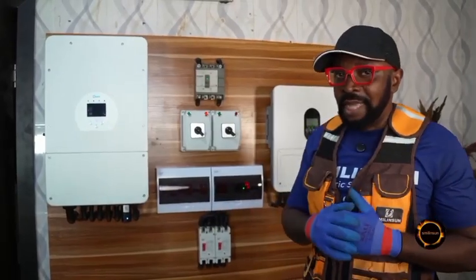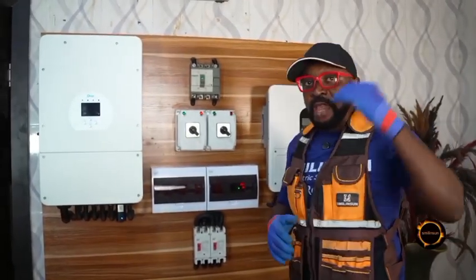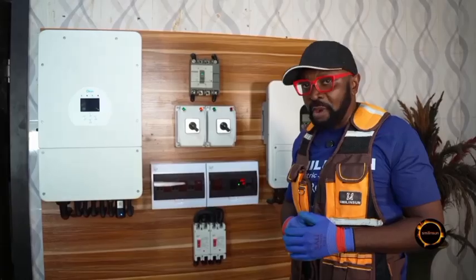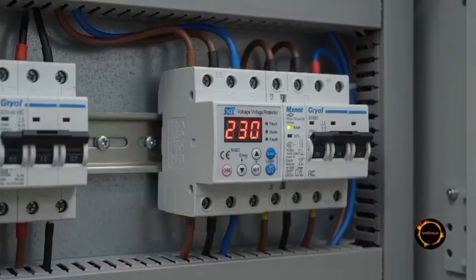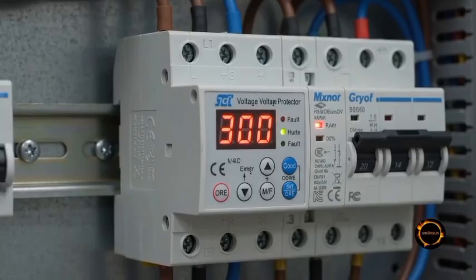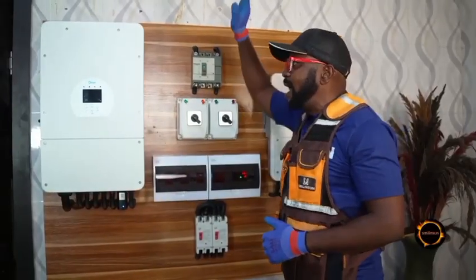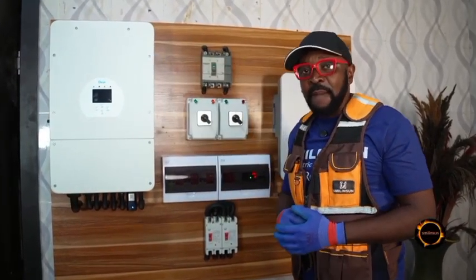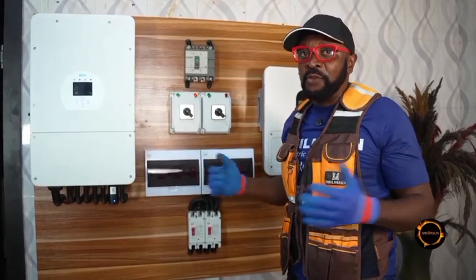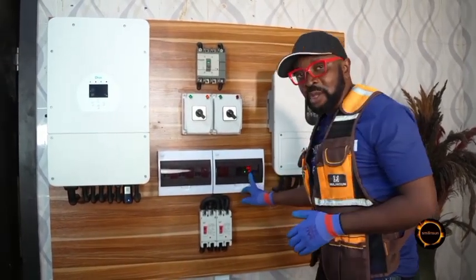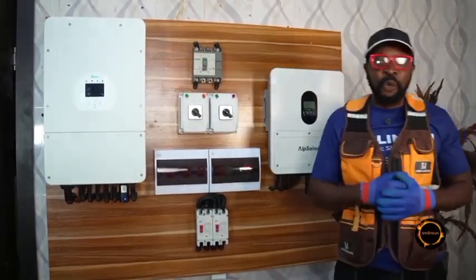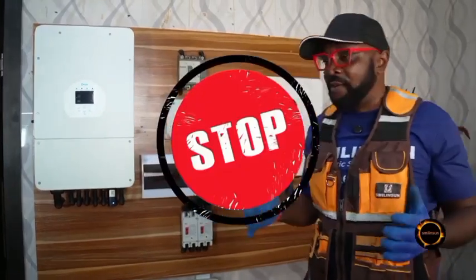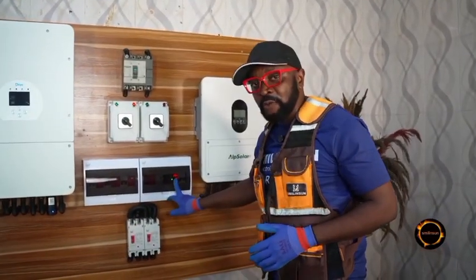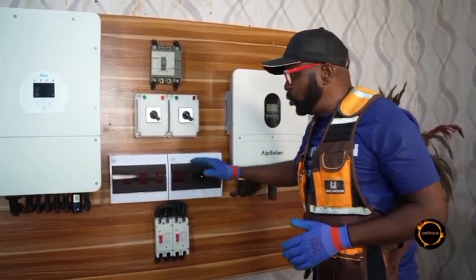If I set the voltage at 260 volts, if the voltage goes above 260 volts, it's not going to let it pass. The worst that can happen is that this device will fry, but it's not going to let that voltage pass through the system and penetrate your inverter. The same thing happens when the current is way over the threshold, and for this one it's just 60 amps. So if the current is above 60 amps, it's going to cut it off. This is also very important, and this forms a huge protective layer to your system.